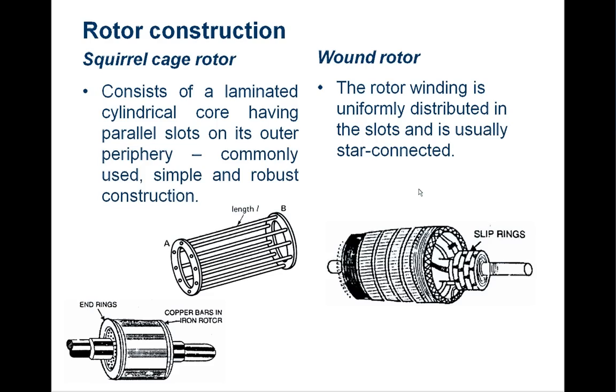For the rotor, there are two ways. The first is the wound rotor, where you get a winding on the rotor. There are three slip rings and three windings equally spaced — just like the stator — wound around the rotor.